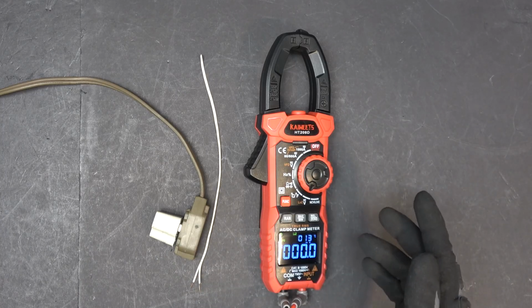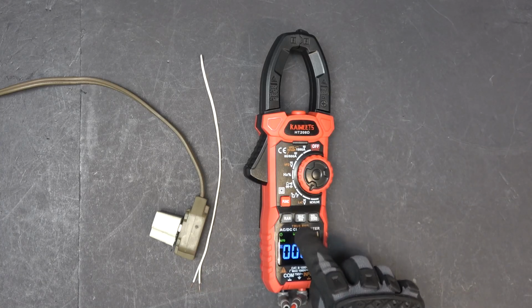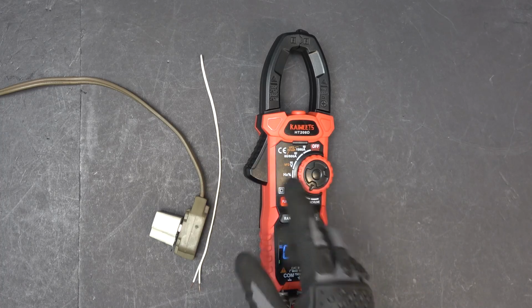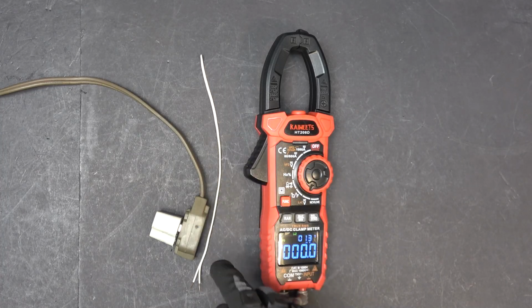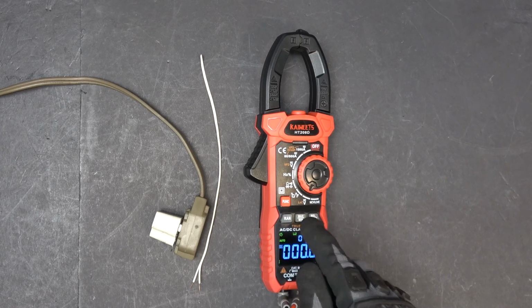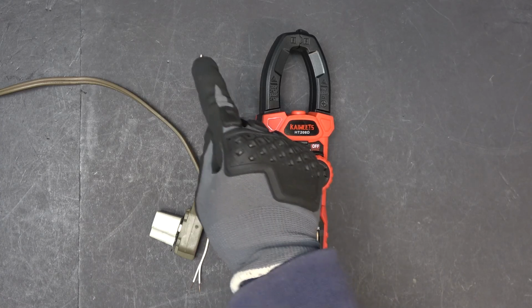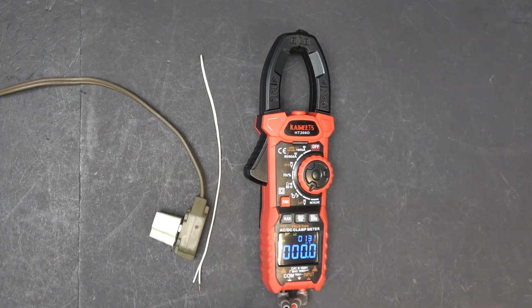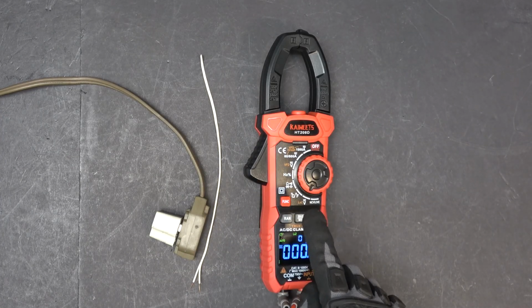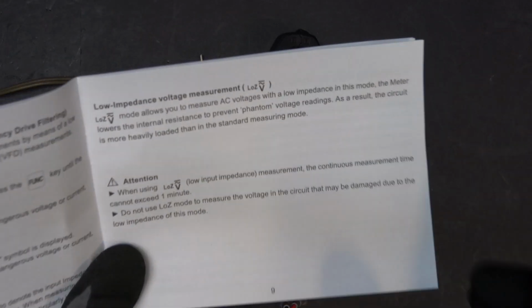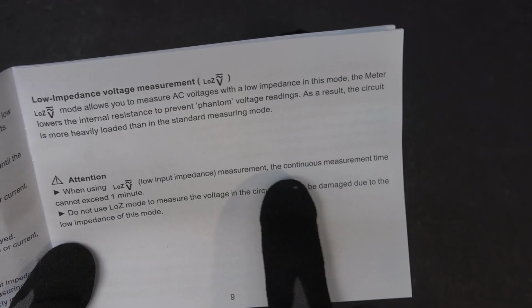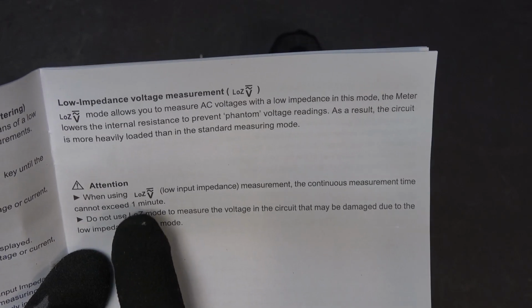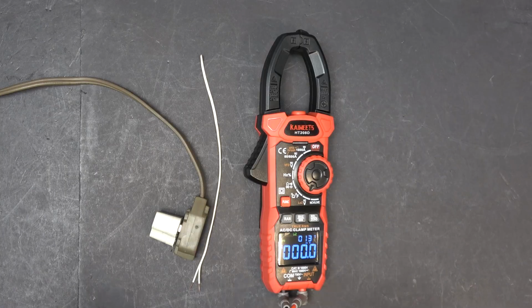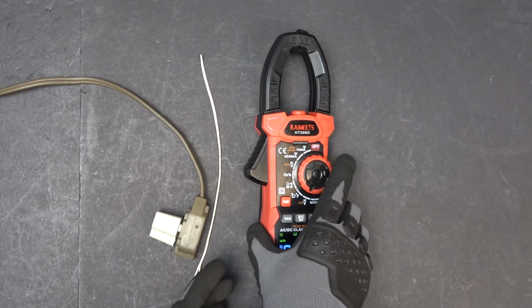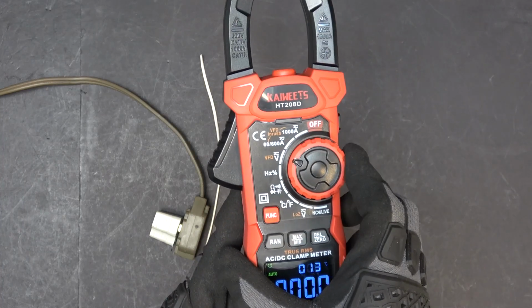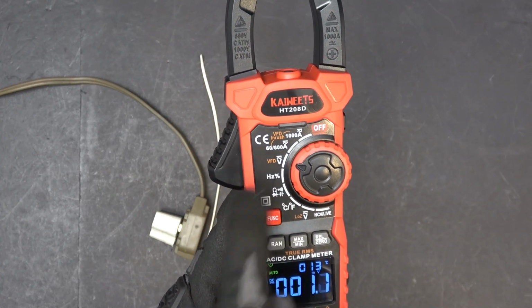So I want to confirm that by using the low Z filter, and it will filter out all these ghost voltages, and it should show 0 on your meter to confirm that there's no voltages in this white wire. And because in this mode the meter lowers the internal resistance, the continuous measurement time cannot exceed 1 minute. So for a regular everyday use, I would just use this option instead to measure voltages.